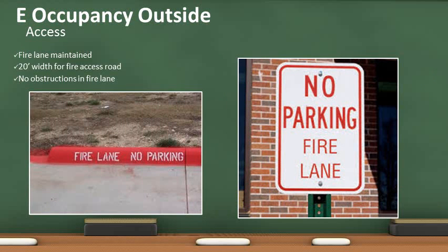Look at the fire lanes. They shall be kept clear at all times and the markings shall be easily identified. Fire lanes are required to be stenciled every 30 feet or have signs every 100 feet facing traffic.